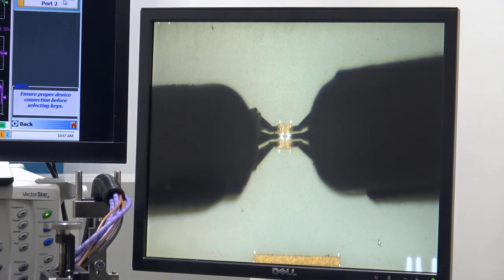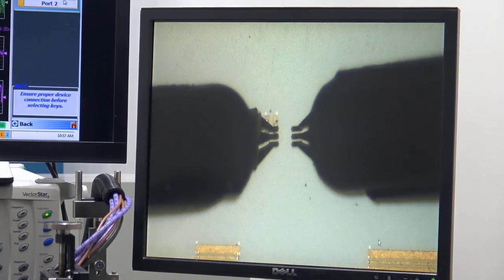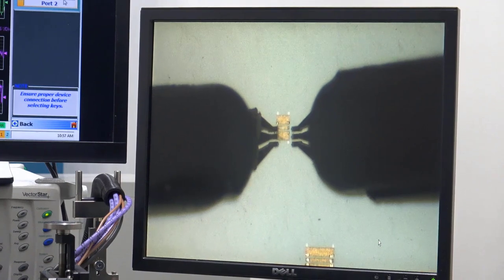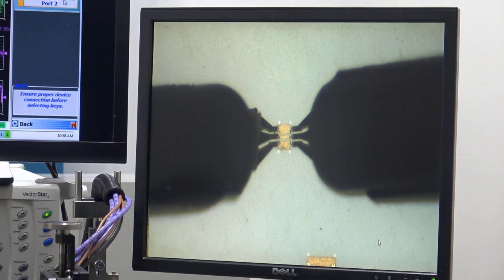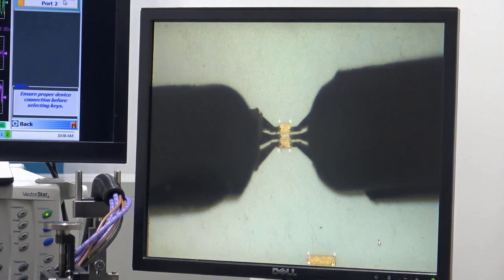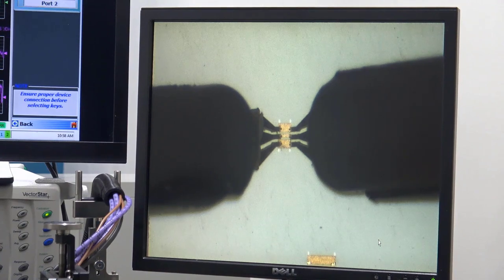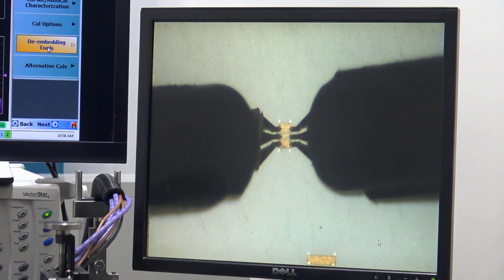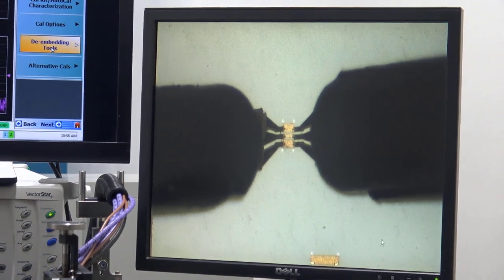Lift our probes and now go to our line. Touch down on our line, make that measurement. And now we can click done and start evaluation of our calibration.